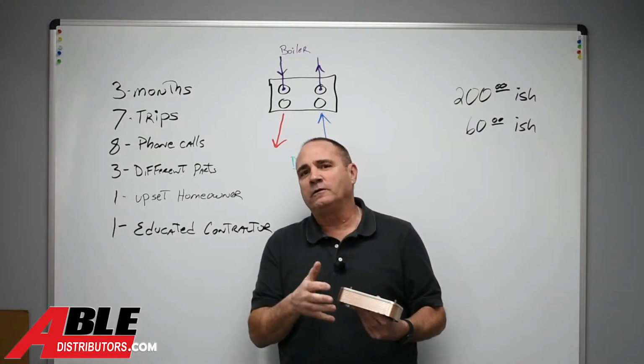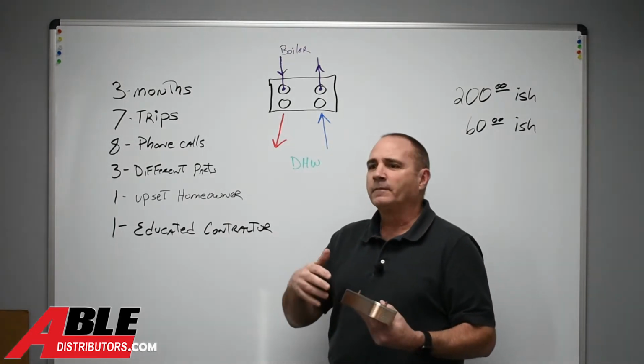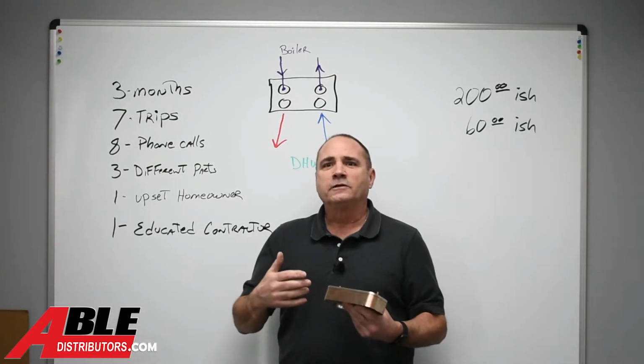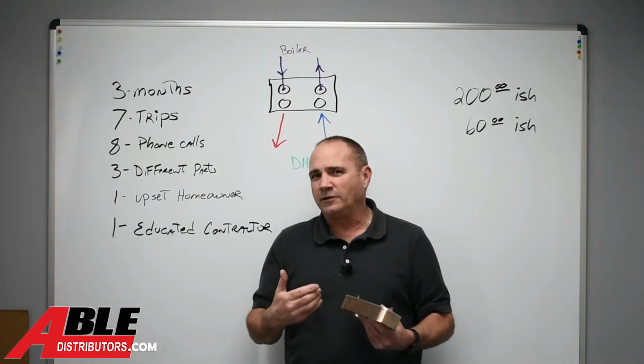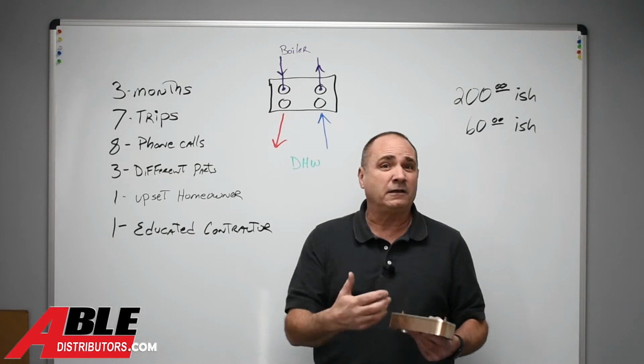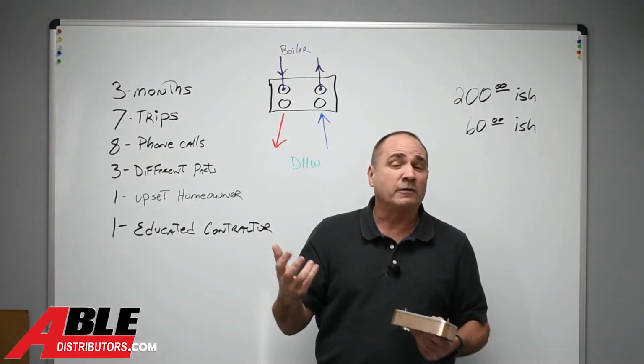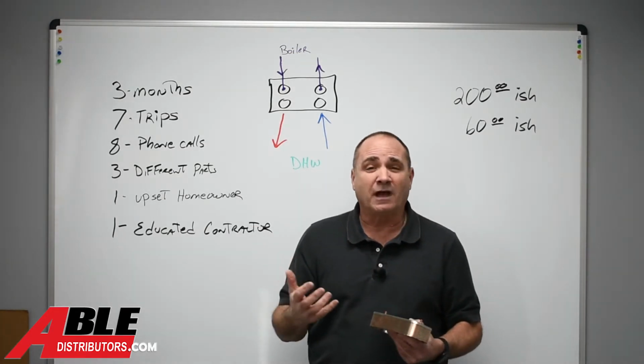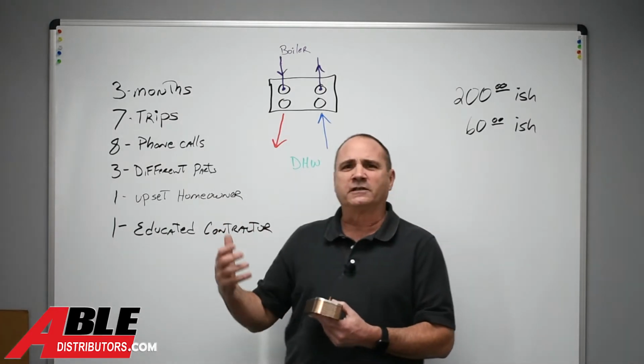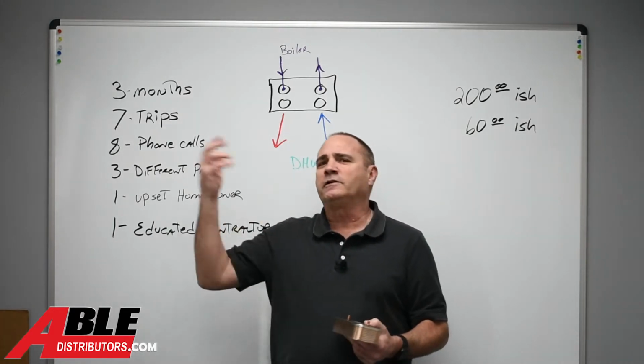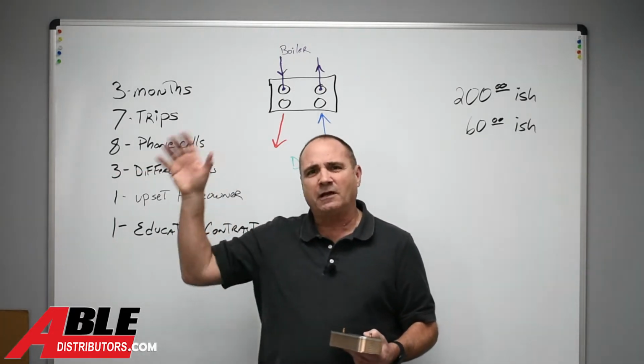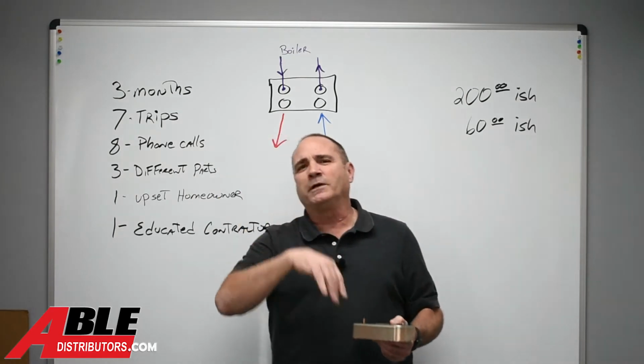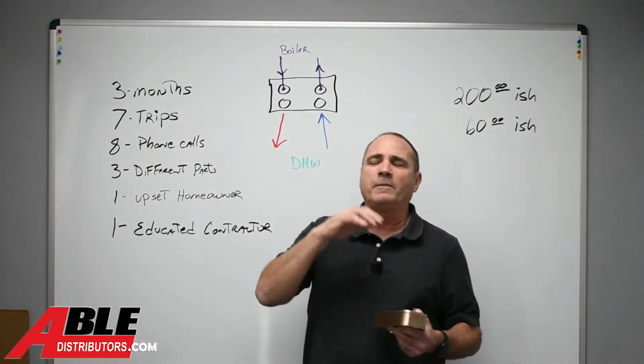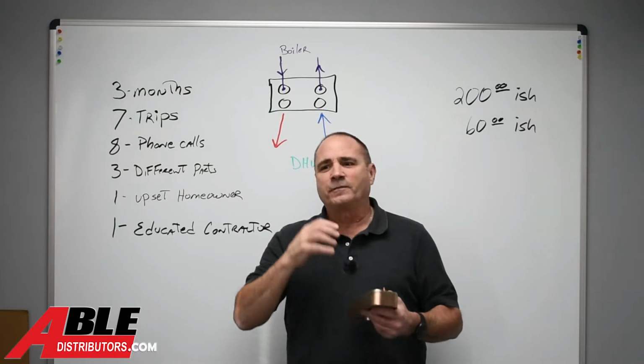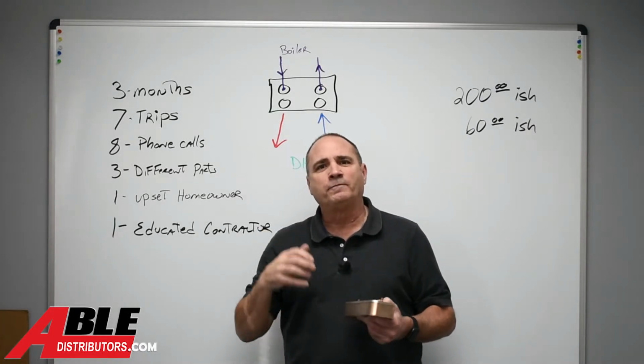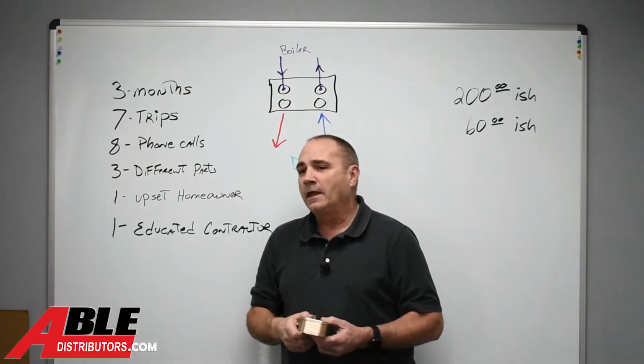It was a copper fin tube, not that old of a system, not that big a house, so it's not typically one you'd think about flushing and cleaning up, caring about the water quality, because it's kind of a simple job. Typically when we think about flushing a system, we think something that's 100 years old with ginormous pipes and cast iron radiators and a big old steam boiler that you have to clean up. Not the case. This was a fin tube, 1,000 square foot home, and I'm going to go over some of the numbers.